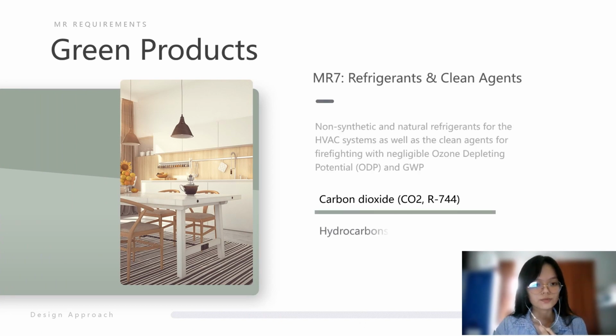A green hospital is proposed to be designed with the application of ecologically sustainable refrigerants and clean agents. To comply with GBI, non-synthetic and natural refrigerants for the HVAC system, as well as clean agents for firefighting with negligible ozone depleting potential and global warming potential, are utilized in the proposed hospital. The most widespread natural refrigerants applied in the HVAC system are carbon dioxide and hydrocarbons such as propane.